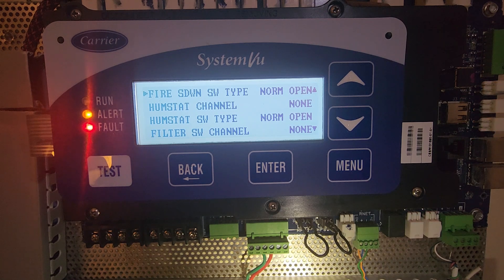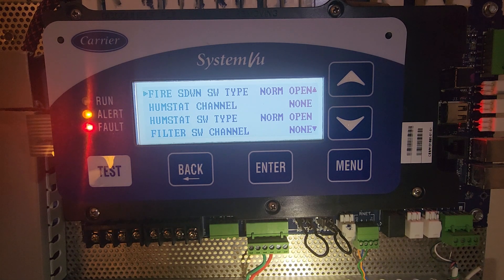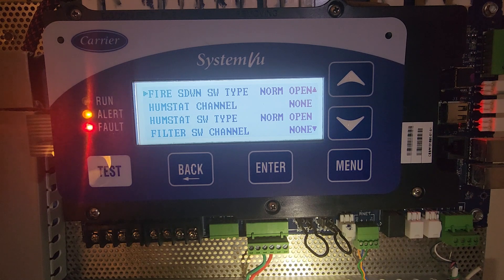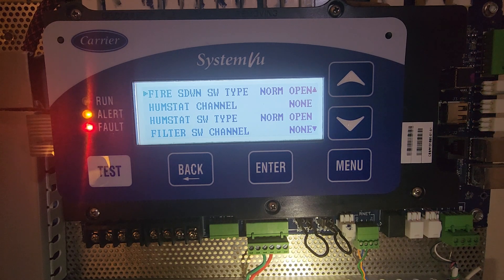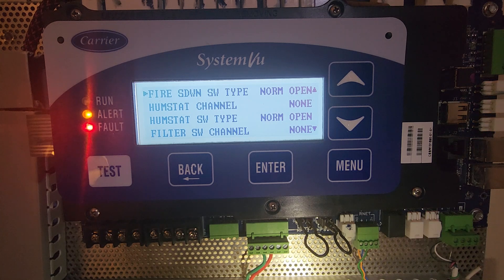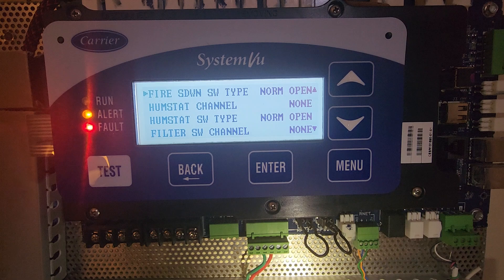In the case of a smoke event, the switch is going to close and the SystemVu will see it and send my unit into alarm. The setup of the field installed smoke detector is complete with SystemVu.